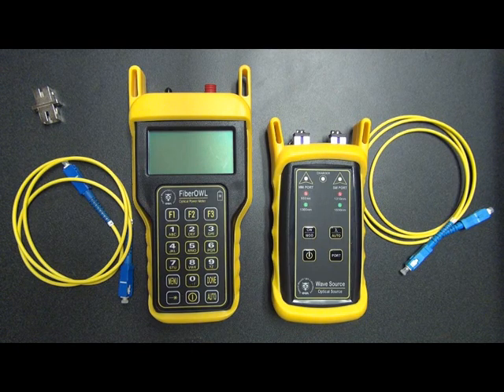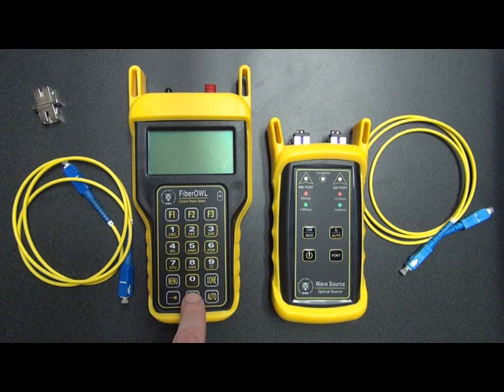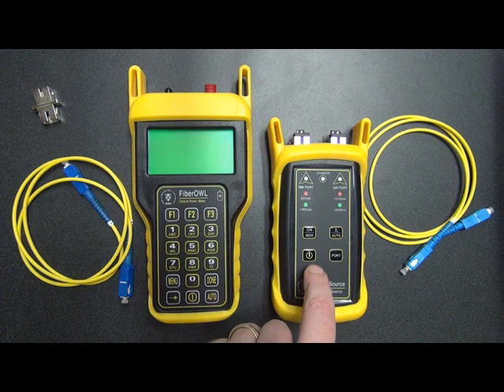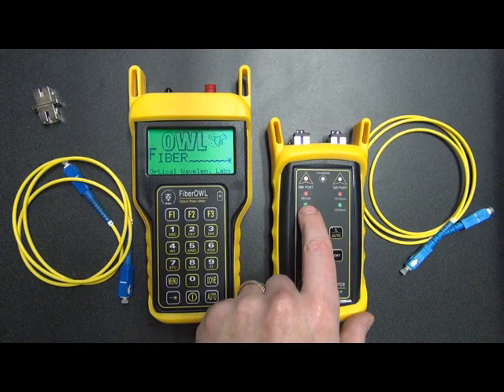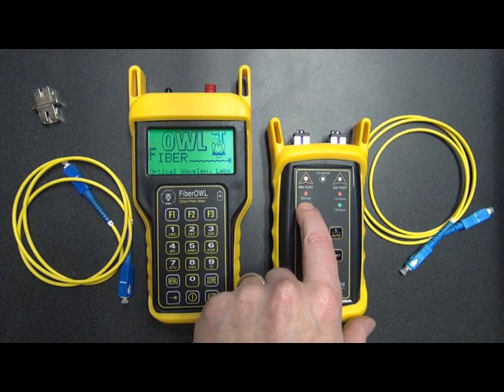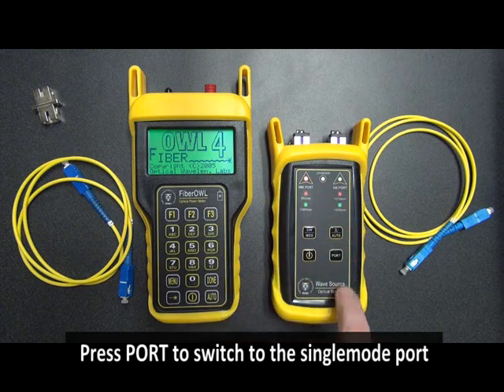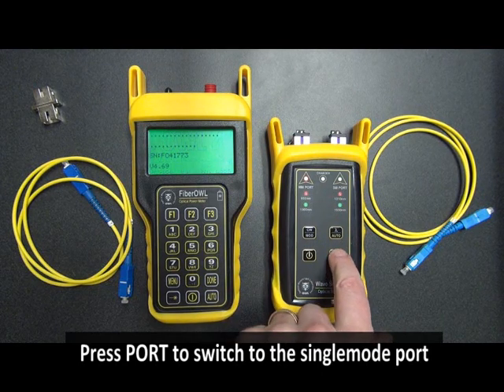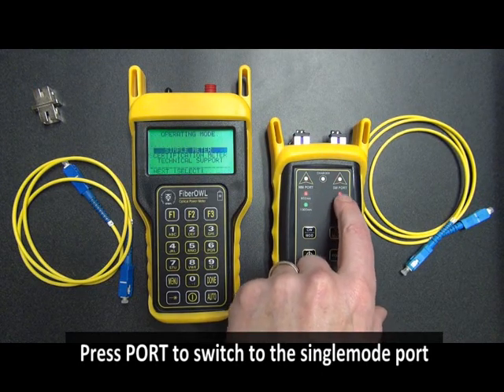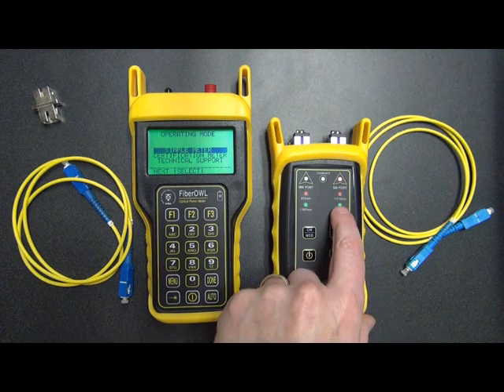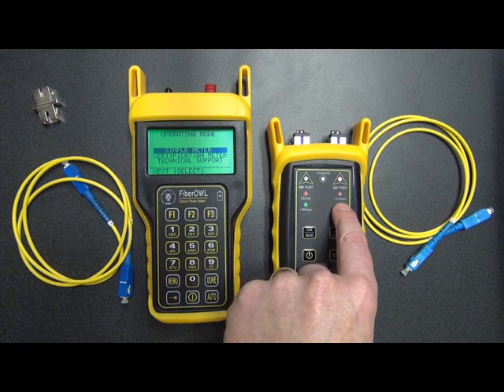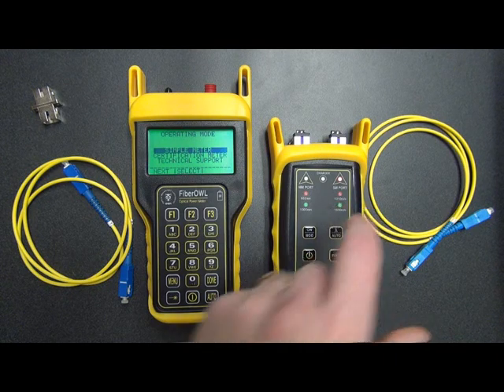The first step is to power on both testers. You press the power button on the Fiber Owl and the power button on the wave source. On the wave source, you'll notice that the multi-mode port is lit by default, so we need to switch to the single-mode port by pressing the port button. You'll notice that the indicator LED here is red, and that means that we're outputting 1310 nanometers at this point.